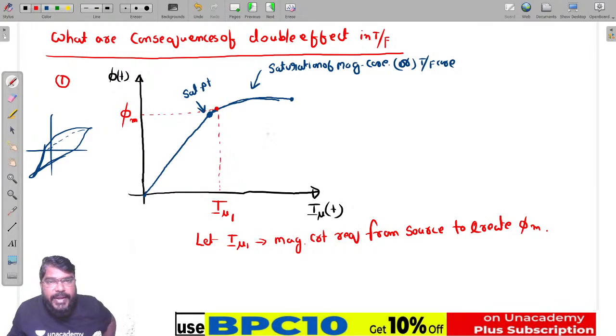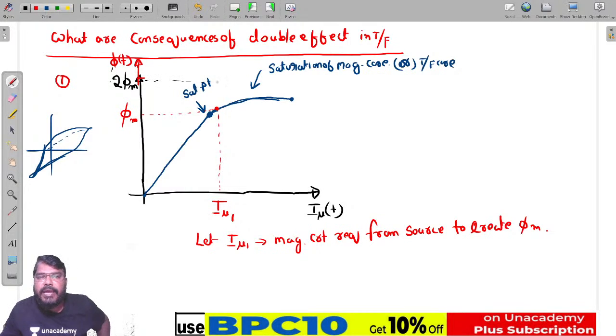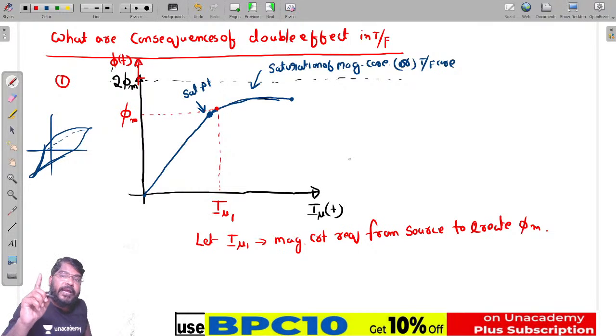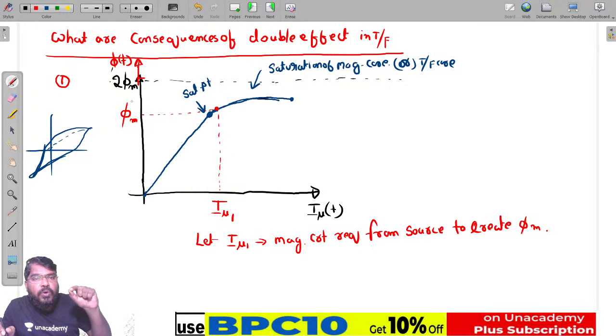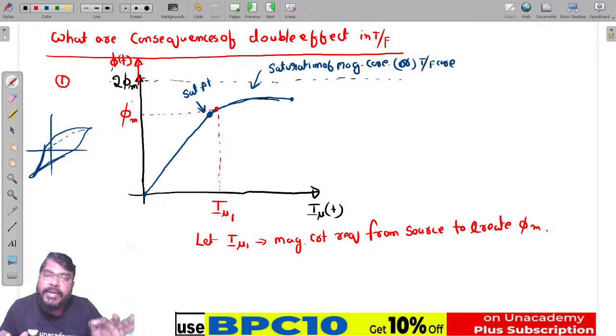Suppose we get 2 times the maximum flux value, phi m, represented as phi of t. In order to get 2 times the maximum flux, the transformer core goes into deep saturation, which demands high magnetizing current from the source. So at the time of switching, in order to produce 2 times the maximum flux, the transformer core goes into deep saturation, and this current is known as the magnetic inrush current.